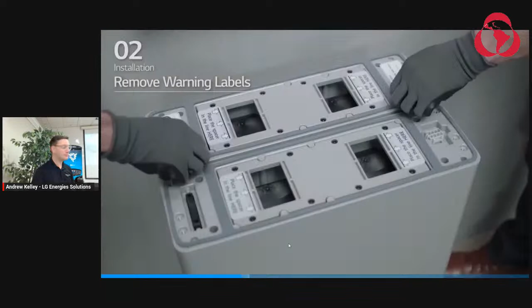From here, these stickers - if you're not assembling the battery right away, maybe you're leaving the job site, keep the stickers on. Dust, moisture, debris can get in there and cause connection issues. That's a common failure point - people remove the stickers too early, things get in there, and then there's a failure. So be careful of the environment you're installing in, and make sure you keep those connectors clean.